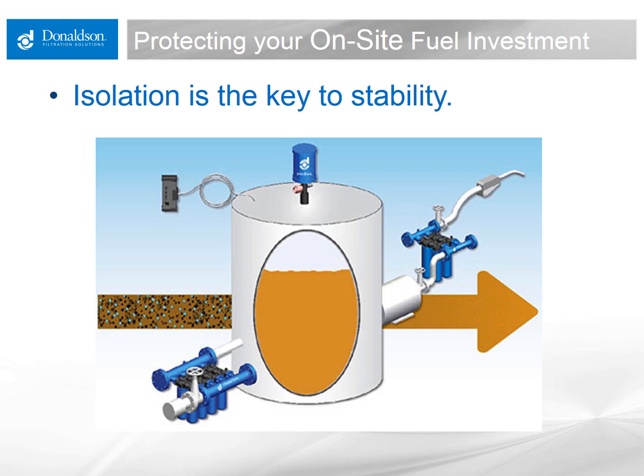The possibility, if it exists, if you have a dry air source, you can purge the top of that tank reservoir and prevent any moisture from collecting on that headspace and draining down into your fuel, and keeping your fuel nice and dry. It will have the best chance to be usable when you need to use it in the winter. And then just filtration on the way out to make sure you're not transferring any issues in your fuel storage tank onto your equipment. Perhaps water that is condensed and the pump picks it up. You could absorb it on the way out.